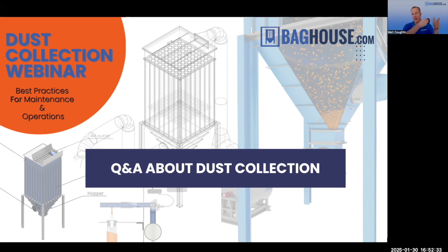If you're returning air back into the building, you would also need isolation on that side. And then you would need some sort of explosion rated or combustible dust rated discharge device, like a rotary airlock or an explosion proof drum kit.